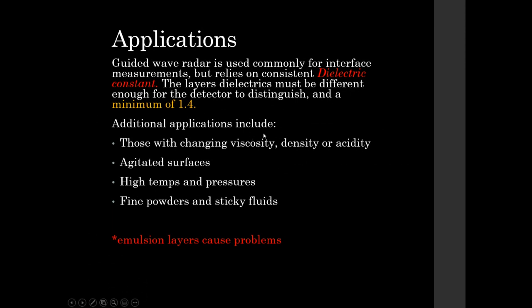Okay, additional applications for radar, those applications where there's changing viscosity, density, or acidity, agitated surfaces, high temperatures and pressures, fine powders, and sticky fluids. These are all great applications for guided wave radar.